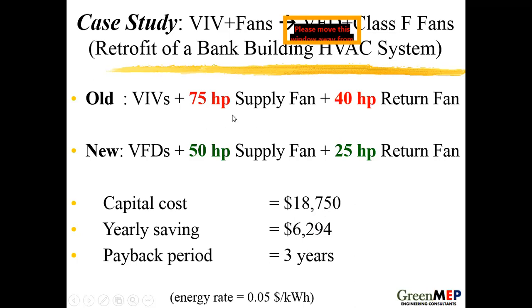By saving the energy bill, the electricity bill, you can see it happens in many ways. Even the size of the fan motor is reduced. A 75 horsepower supply fan, now you only need 50 horsepower, right? A 40 horsepower return fan, we need only 25 horsepower.